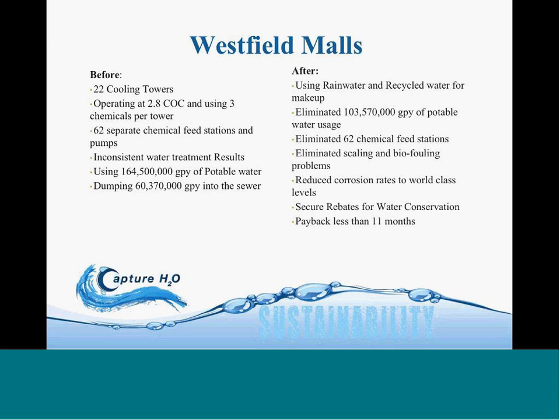2.8 cycles of concentration is roughly 35% of the water blown down to the sewer. They had 62 chemical feed stations and pumps, and they had inconsistent water treatment results, meaning every couple of years a different mall would have scale in their chillers or bacteria or high corrosion rates. So the results weren't steady and consistent. They were using 164 million gallons of potable water and dumping about 60 million gallons back to the sewer.